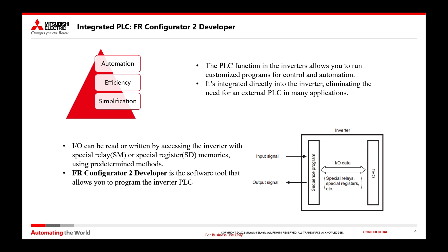The inverter becomes a smarter device, allowing us to create custom logic. In addition, you have a more compact and less expensive hardware configuration, eliminating the need for an external PLC for many applications. At the bottom right we find the block diagram of the inverter operation, where the inputs and outputs can be read or written by accessing with the special relays or with the special registers. Finally, the software tool that we will use to program the inverter PLC is the FR Configurator 2 Developer.